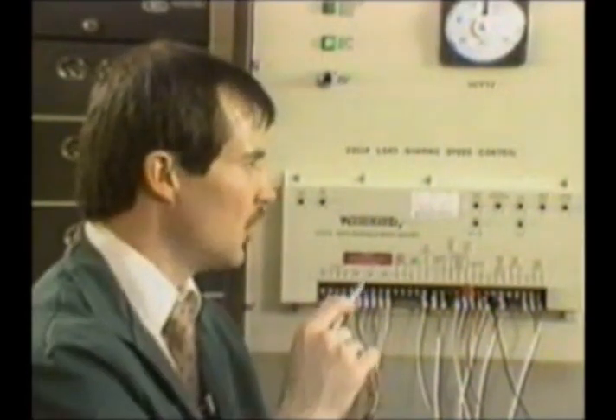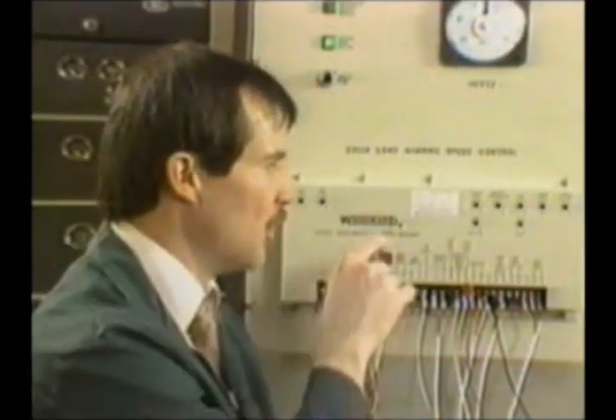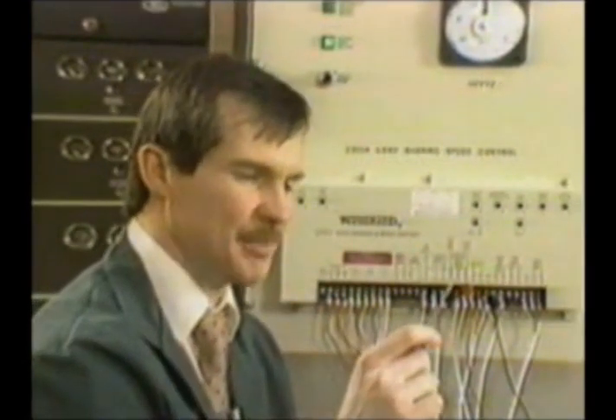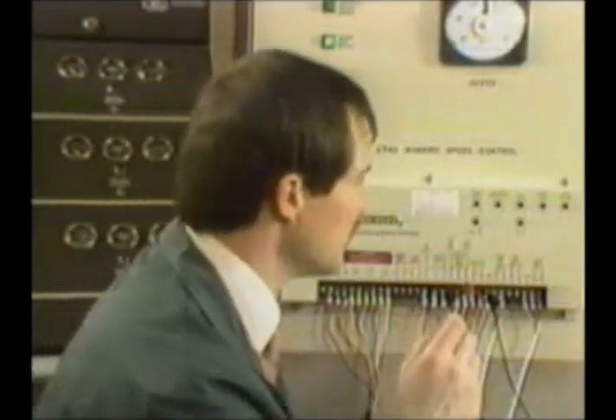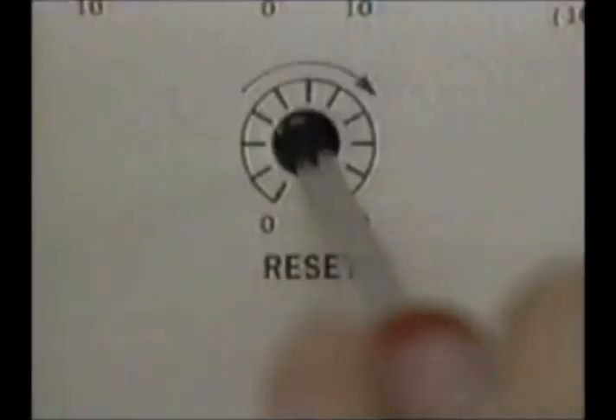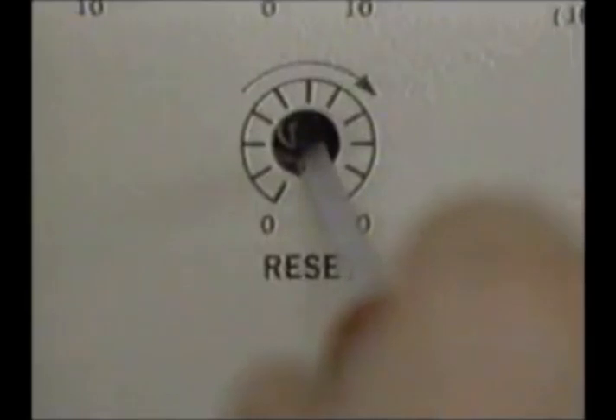The gain will catch your off speed, and the reset will decide how quickly you come back and set up at your rated speed. So what I know with that reset pot turned fully clockwise, once we go off speed, it will be really slow coming back to speed. So I'm going to set this up to mid-range again, or number 5 on the dial.